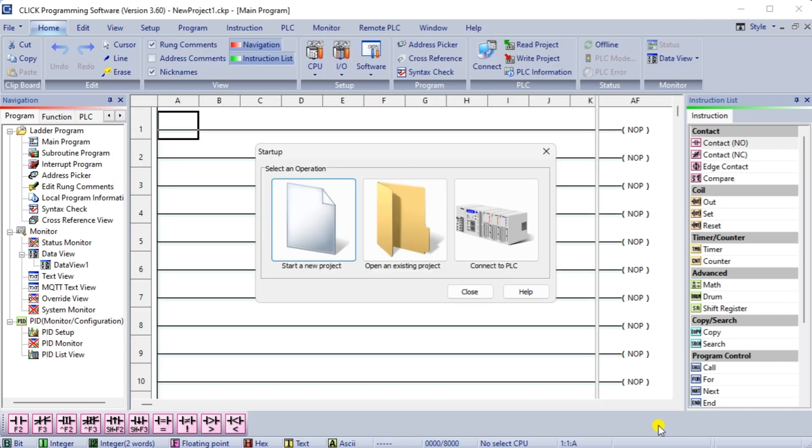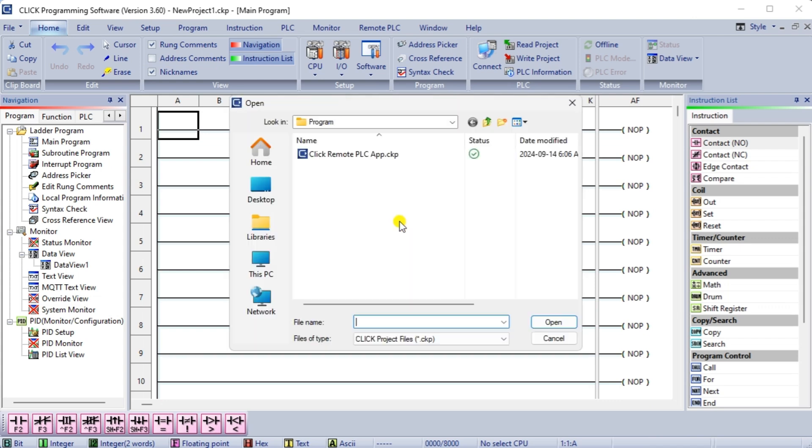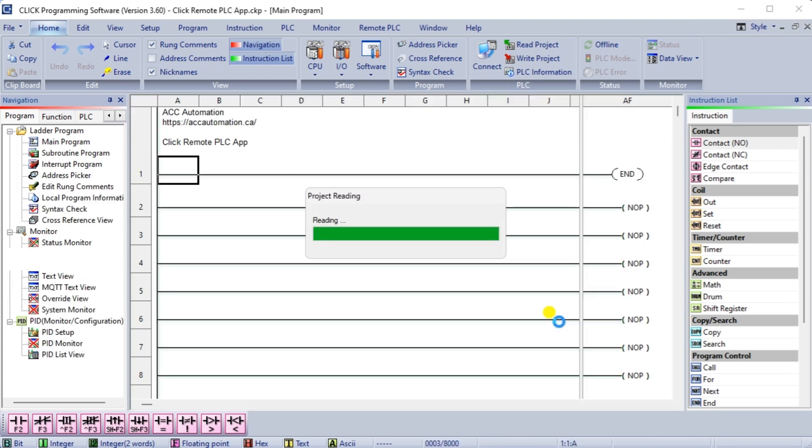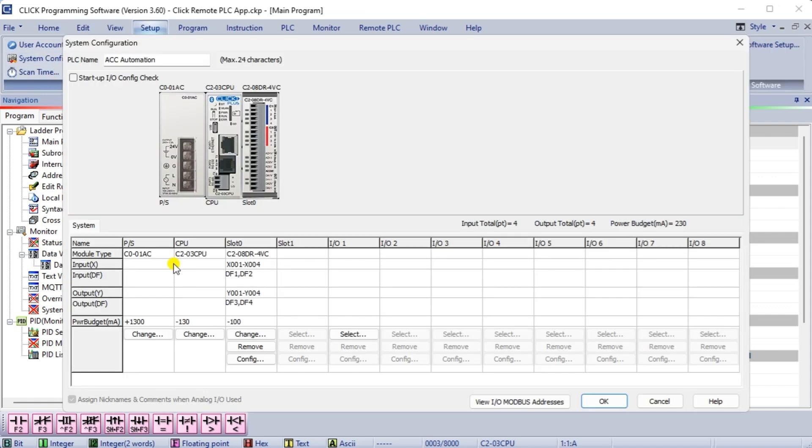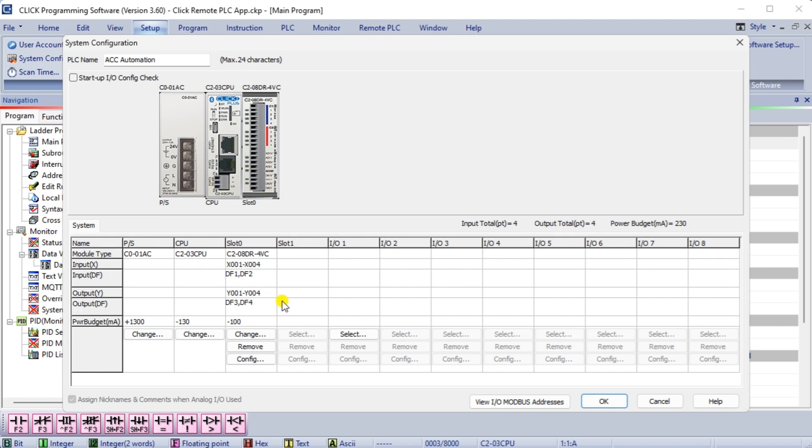When the startup window displays, we will select open existing project. Select the Click Remote PLC App and select open. This program consists of just an end statement for the program and is configured for our hardware. Select system configuration from the main menu setup. This will show you that we have a C2-03 CPU with a power supply and a C2-08DR-4VC slot card. Our discrete inputs are X1 to X4 and analog are DF1 and DF2. The discrete outputs are Y1 to Y4 and the analog are DF3 and DF4.